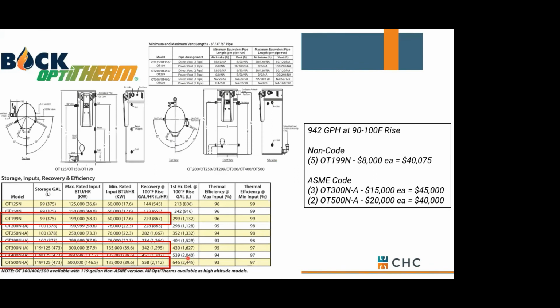Well, I don't represent A.O. Smith, so I might go to a product that I do represent called Bock. And Bock makes a tank type water heater. Now I've got some options here if I'm trying to recover 942 gallons per hour. I can go with some non-code units. In this case, I'm going to need 5 of them to give me 942. They come in at a cost of about $8,000 each, or a total of $40,000.